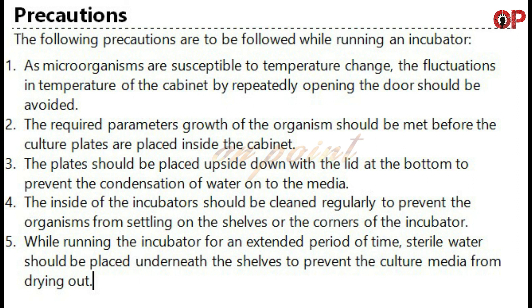3. The plates should be placed upside down with the lid at the bottom to prevent the condensation of water onto the media. 4. The inside of the incubators should be cleaned regularly to prevent the organisms from settling on the shelves or the corners of the incubator. 5. While running the incubator for an extended period of time, sterile water should be placed underneath the shelves to prevent the culture media from drying out.